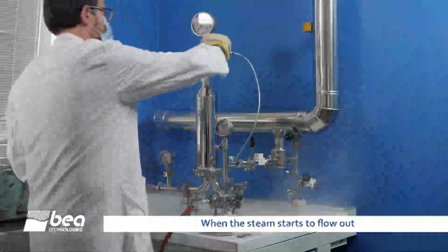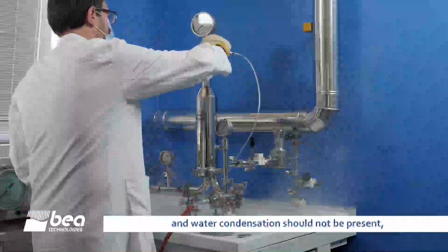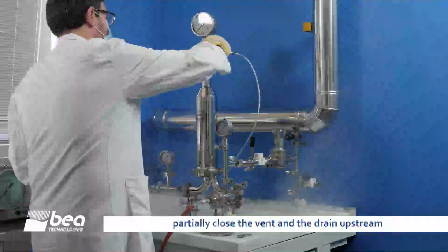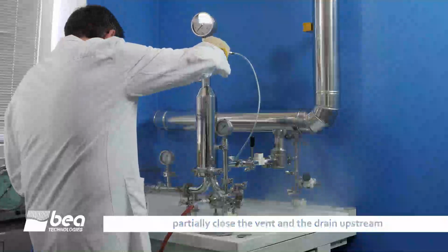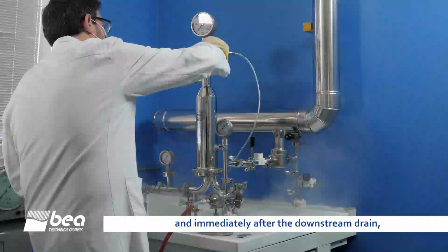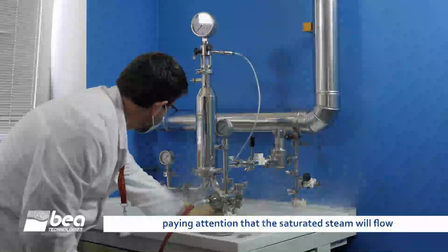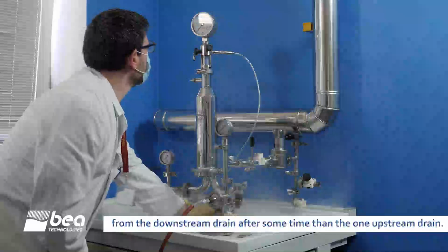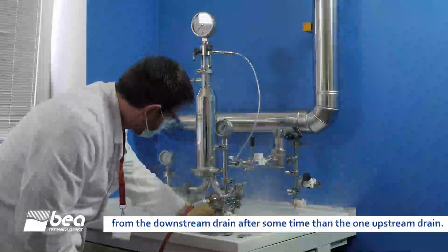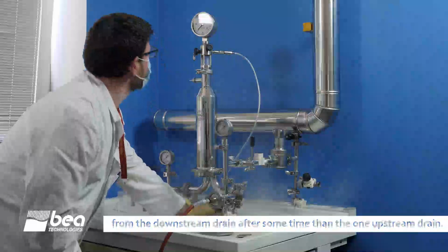When the steam starts to flow out and water condensation is no longer present, partially close the vent and the drain upstream, and immediately after the downstream drain, paying attention that the saturated steam will flow from the downstream drain after some time rather than from the upstream drain.